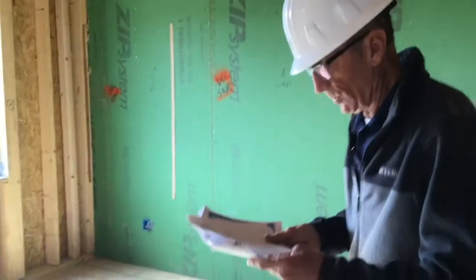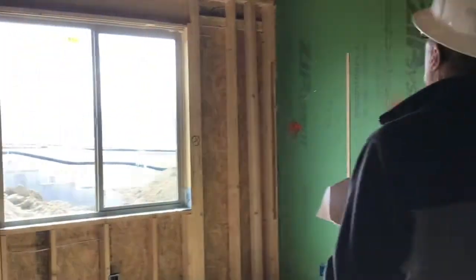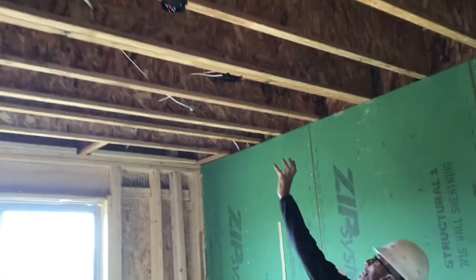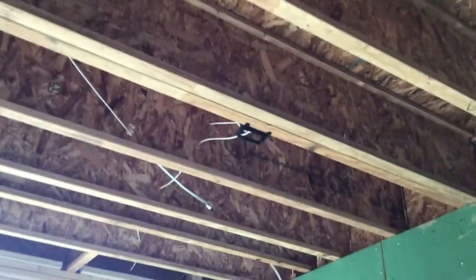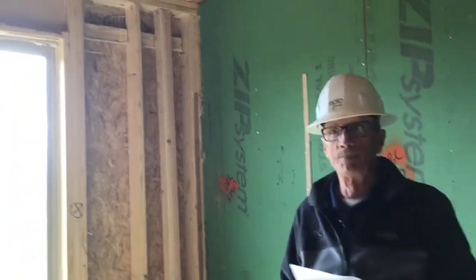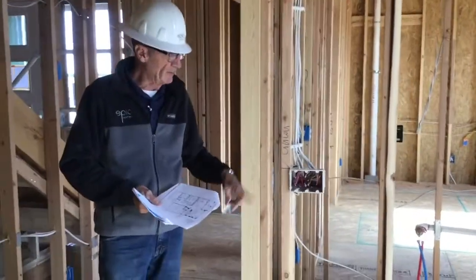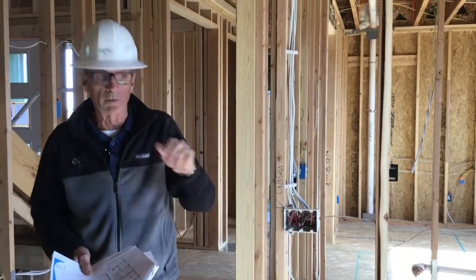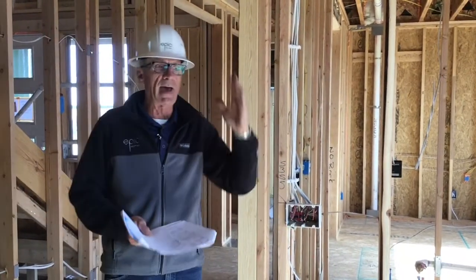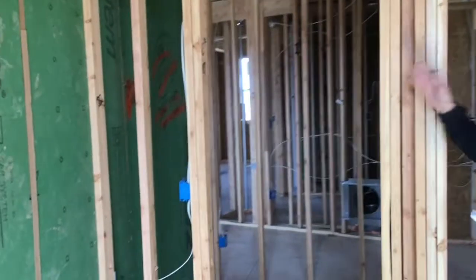Also in the guest bedroom, you have requested a wireless access point, and that's this black box with Cat 6 to it. So that is the WAP 6 pre-wire. So in the room, at the entrance to the bedroom, we've got 3 switches going on here. Number 1, turn the travelers off behind yourself. Number 2, we've got a ceiling fan pre-wire with 2 switches on one, and the half hot across the room. Got the walk-in closet with a switch inside the door to a can light in the ceiling.